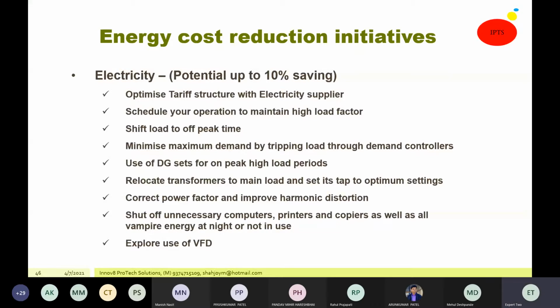Number one is optimization of tariff structure, so that you utilize the energy at the lowest price. Number two, you should have some load shedding exercise in the complex so that you do not consume peak energy. You may use DG sets in some places when your peak load comes, and you have to relocate the transformer to the main load. Your cable loss is I square R. So if your I is increasing because of the reduction in the voltages, then your losses are increasing. If you locate your transformer at a far away location, a high current cable is laid, and that leads to the losses.